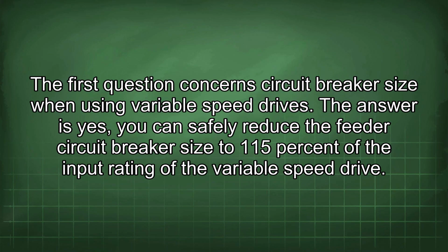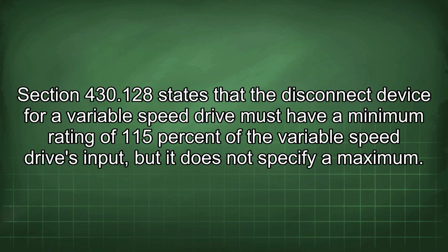First question concerns circuit breaker size when using variable speed drives. The answer is yes. You can safely reduce the feeder circuit breaker size to 115% of the input rating of the variable speed drive. Section 430.128 states that the disconnect device for a variable speed drive must have a minimum rating of 115% of the variable speed drive's input, but it does not specify a maximum.